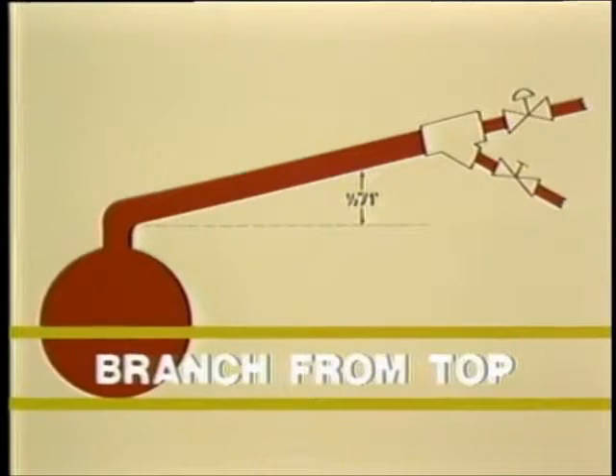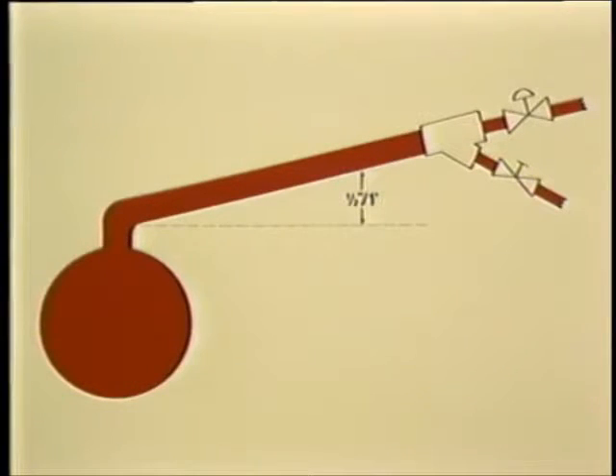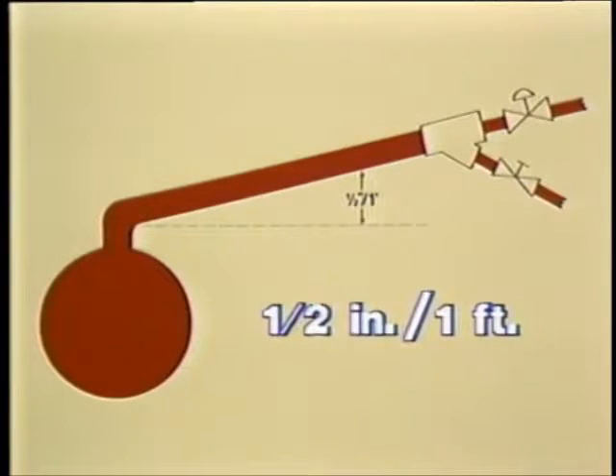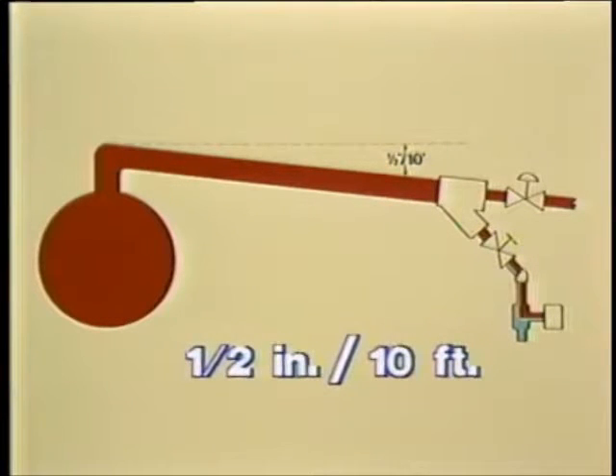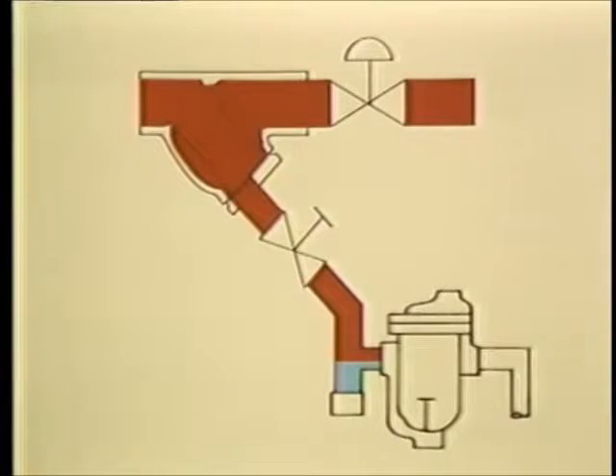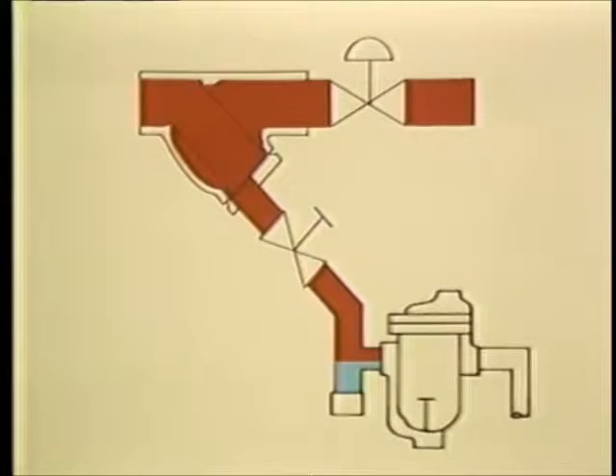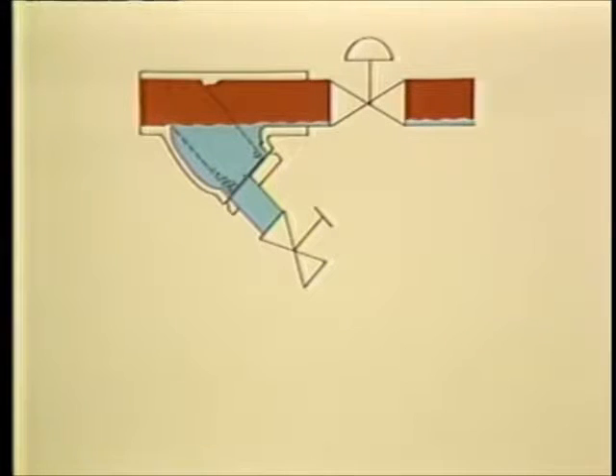Branch piping, or runouts from the steam main, should always be taken from the top of the main. Runouts of less than 10 feet can be pitched up from the main at one half inch per foot and do not require a drip trap ahead of a PRV or control valve. If the runout is more than 10 feet, it should be pitched down from the main, with a strainer and drip trap installed immediately ahead of an automatic control valve or PRV. One practical recommendation is to install the drip trap on the blow-down connection of the strainer ahead of the valve. This arrangement will automatically blow down the strainer while providing the necessary drainage of condensate.